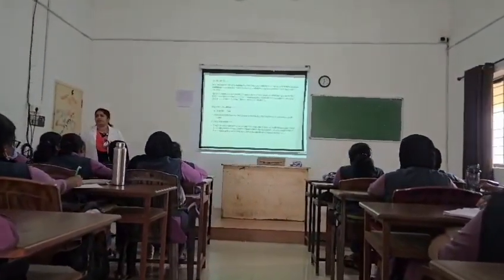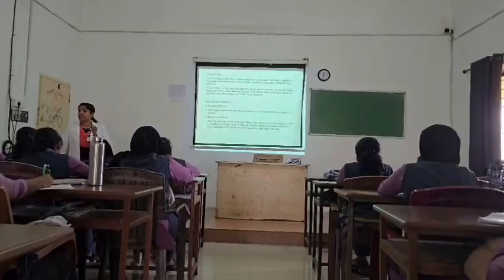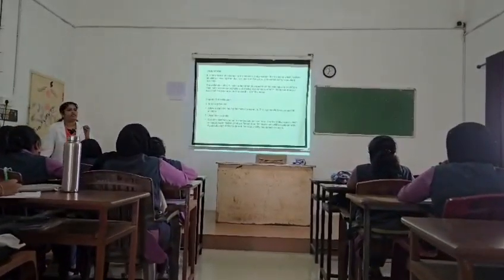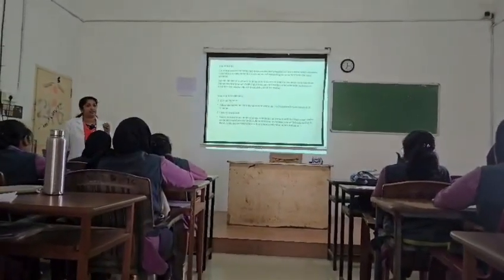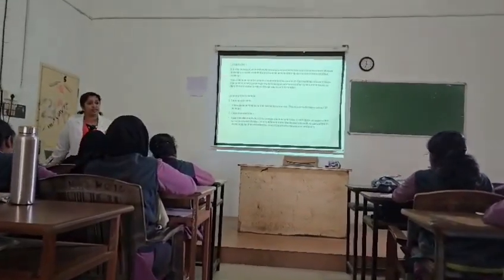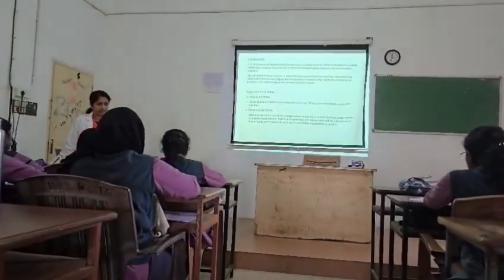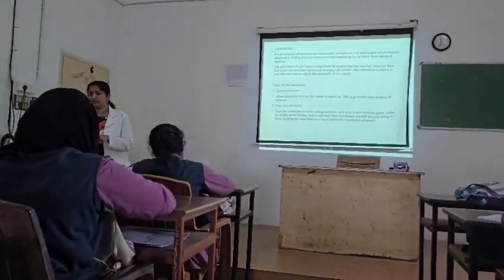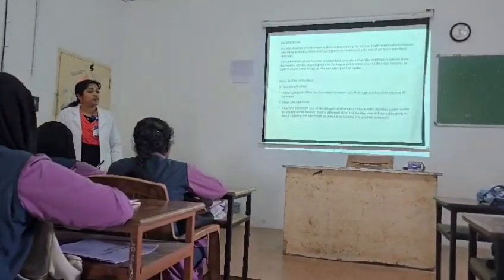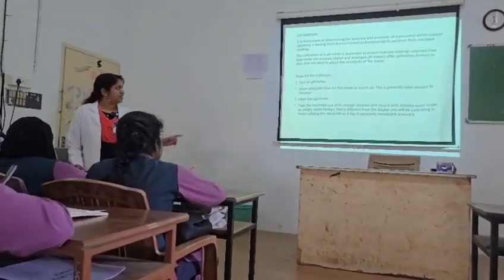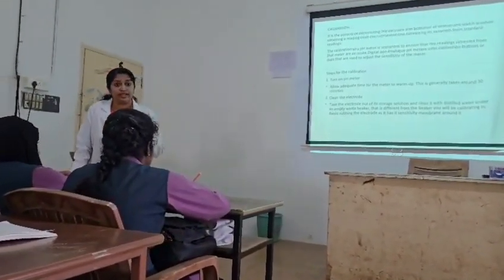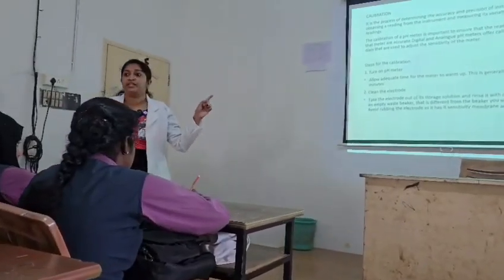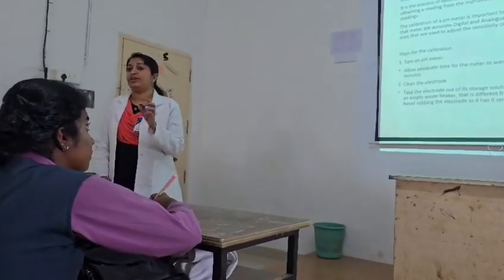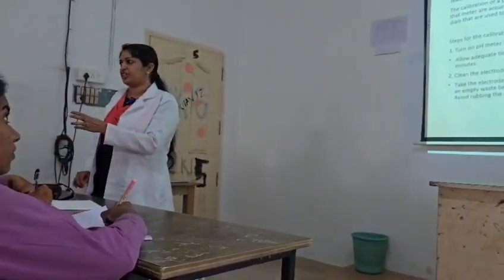Commonly we use a pH meter for the determination of the pH of a sample. Before the measurement of the pH of the sample, we have to calibrate that particular pH meter. The calibration of a pH meter includes different steps. The first step is to turn on the pH meter, which means we switch on the equipment and allow the meter to warm up. Only then will it stabilize and provide a correct result.